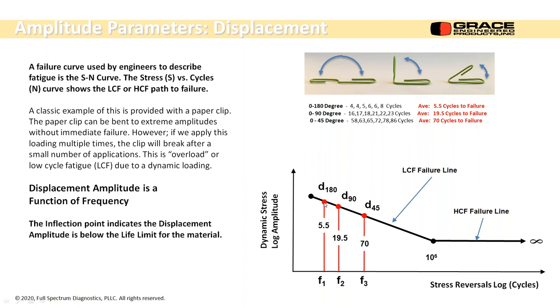Okay, I don't know what the exact value is. I'd need a strain gauge, but do the same thing at a 90 degree bend. It takes much higher cycles to fail. So it lasts over 3 times longer, but its allowable is a little lower. Okay, 19.5 cycles. My amplitude of displacement was half of what it was over here.